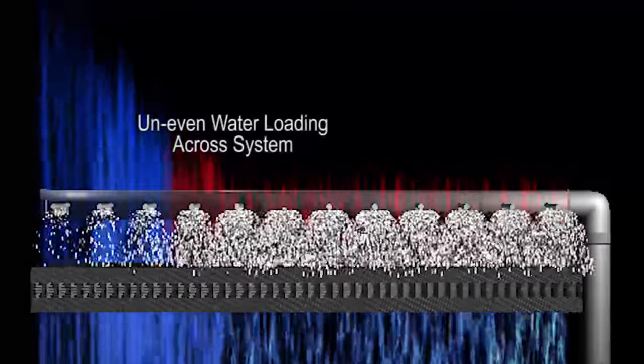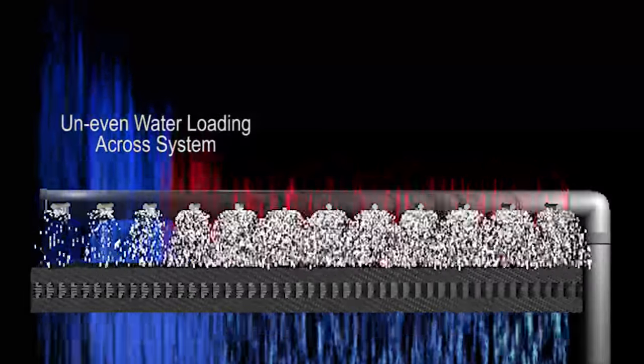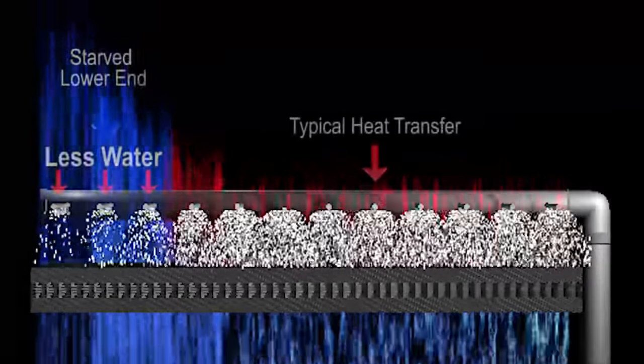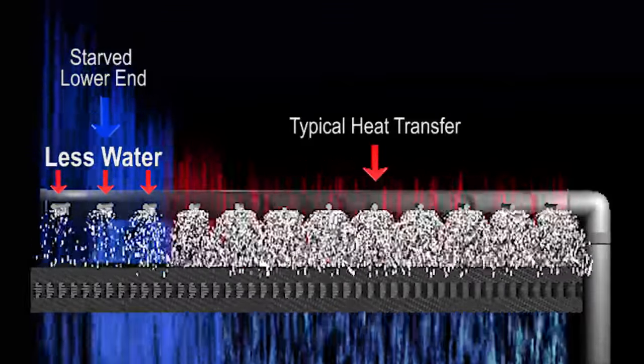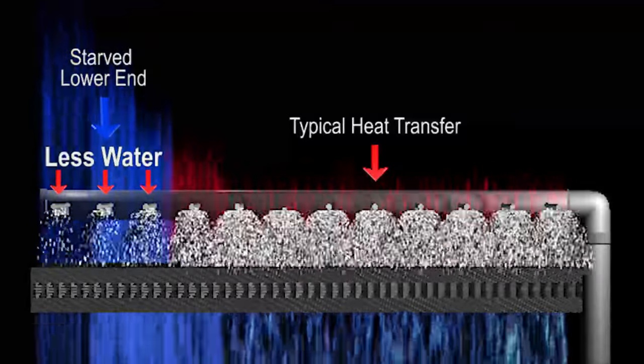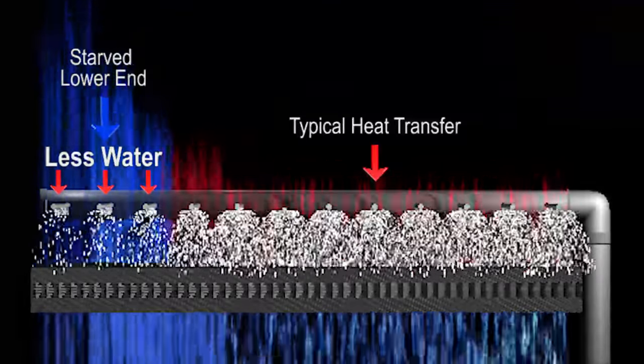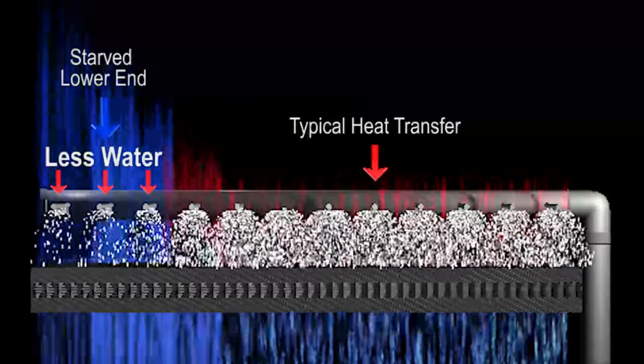The result is uneven water loading across the system, often starving the lower end of the distribution system of water. This results in a waste of both fan and pump energy. In effect, the velocity pressure competes with the static pressure at the nozzle, resulting in the system not becoming fully charged. The net result of this is that no two nozzles receive equal water loading.